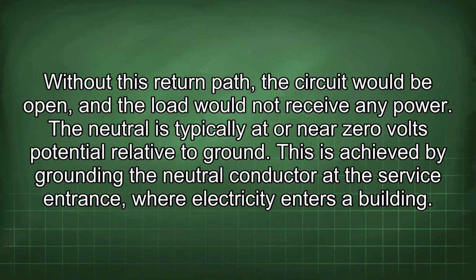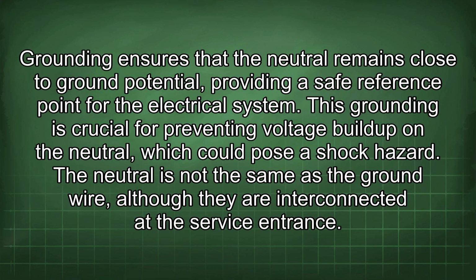The neutral is typically at or near 0 volts potential relative to ground. This is achieved by grounding the neutral conductor at the service entrance, where electricity enters the building. Grounding ensures that the neutral remains close to ground potential, providing a safe reference point for the electrical system. This grounding is crucial for preventing voltage buildup in the neutral, which could pose a shock hazard.